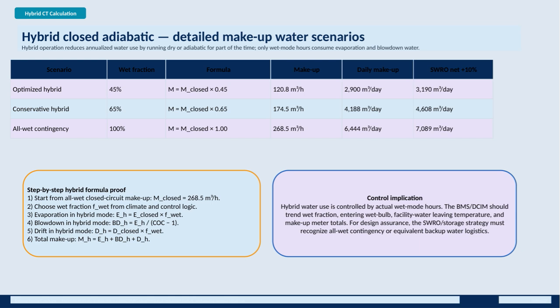The step-by-step formula begins with the all-wet closed-circuit makeup value, then selects a wet fraction based on climate and controls. Evaporation, blowdown, and drift are all scaled by this wet fraction, and the total makeup water is the sum of these components. Finally, from a control perspective, hybrid water usage depends directly on wet mode hours.